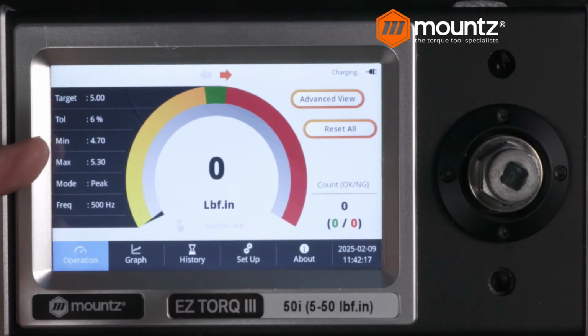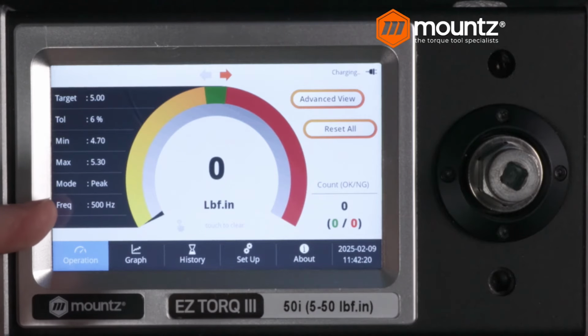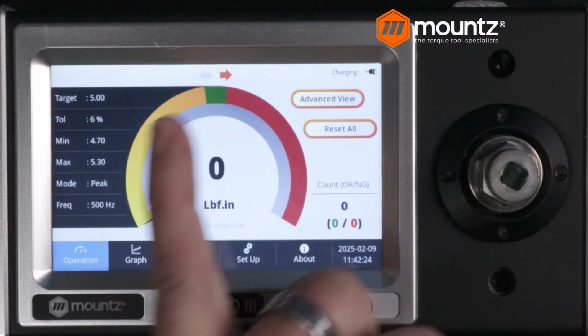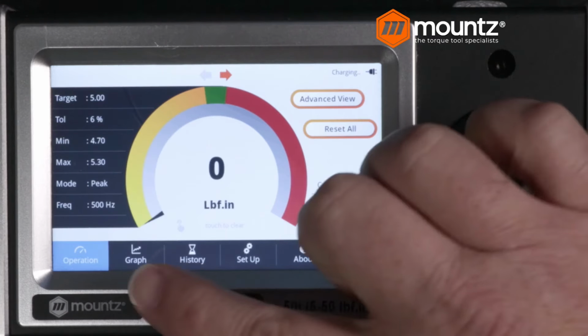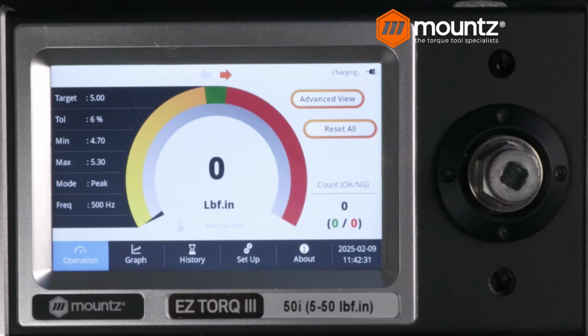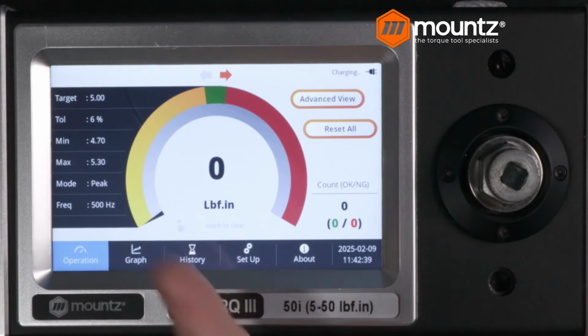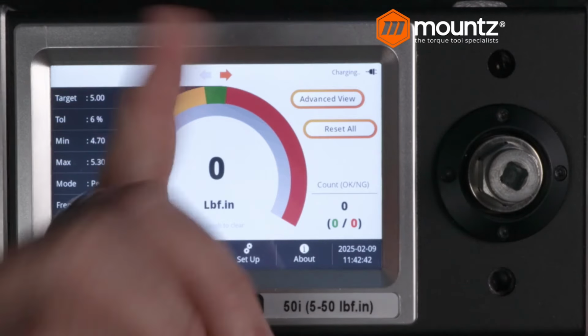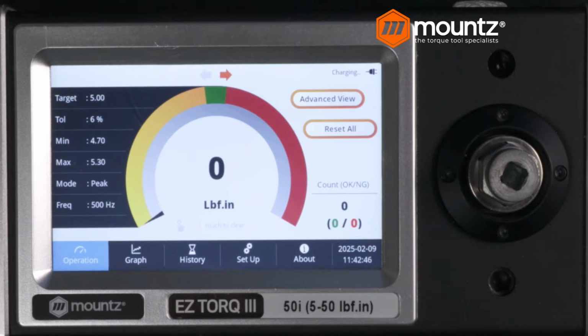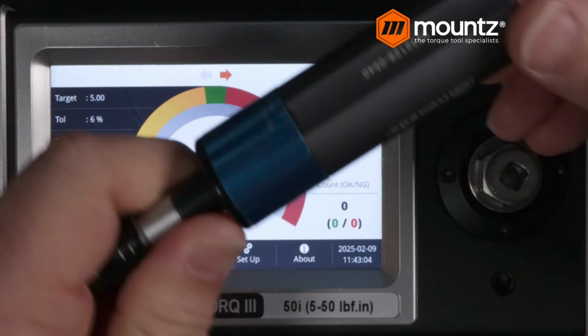And that's going to give us what our minimum value would be, our maximum value, which mode we're using, and our frequency setting. And displayed on the screen here, the acceptable limit is going to be right at 12 o'clock. And then we have a green window, which is our min and our max tolerance. And then anything under that is obviously under, and anything in the red is going to be over that range. Now, it doesn't quite come up on the camera, but there is a transition here from yellow to an orange color as we get closer, but I'm not sure if you can see that as well. But anyway, if we wanted to test a screwdriver, so this is one of our FG torque screwdrivers.